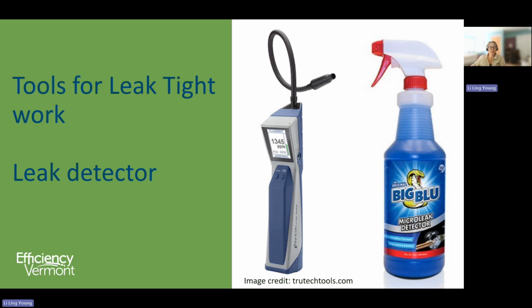There are ultrasonic leak detectors that make it possible to hear a leak. Like leak detection fluid, they can pinpoint a leak. And unfortunately, there's a big learning curve with that kind of leak detector.